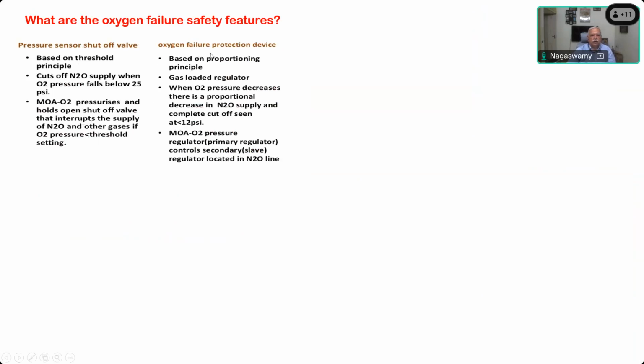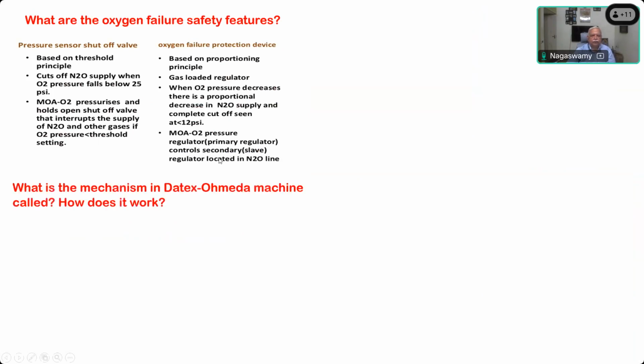In oxygen failure protection devices based on the proportioning principle, a gas-loaded regulator is there. So when oxygen pressure decreases, there is a proportional decrease in nitrous oxide supply, to completely cut off at 12 psi. Here it is 25, here it is 12 psi. The mode of operation is that the oxygen pressure regulator, the primary regulator, controls a secondary or slave regulator located on the nitrous oxide line.